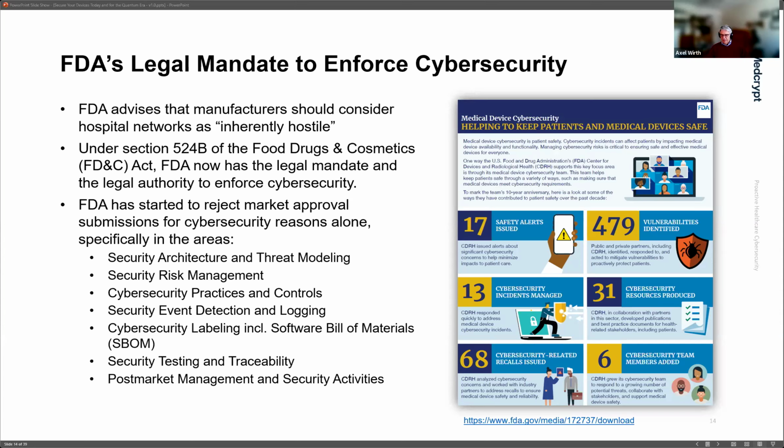And in fact, FDA has made the inclusion of a post-market management plan in your market approval application a condition for market approval. So you not only need to demonstrate to the FDA that your device is secure, but you also need to demonstrate that you have a plan and processes in place to maintain the device's security risk once it is market released. Next slide, please.